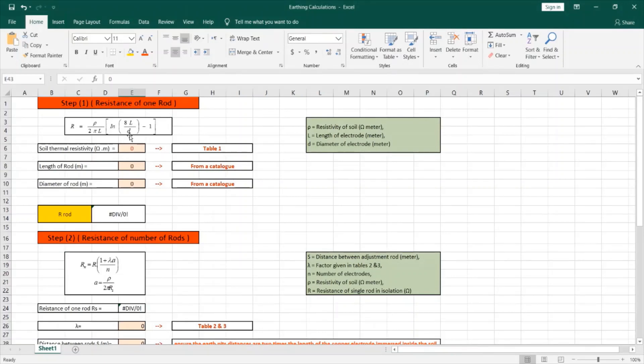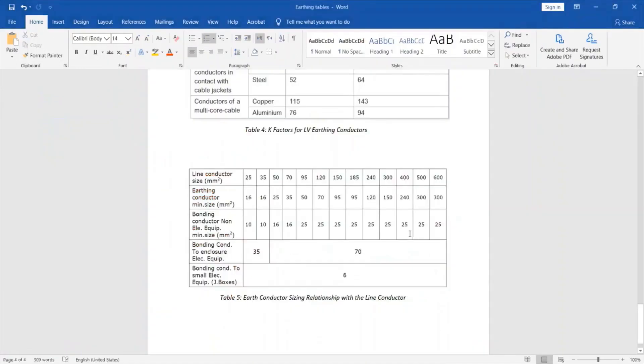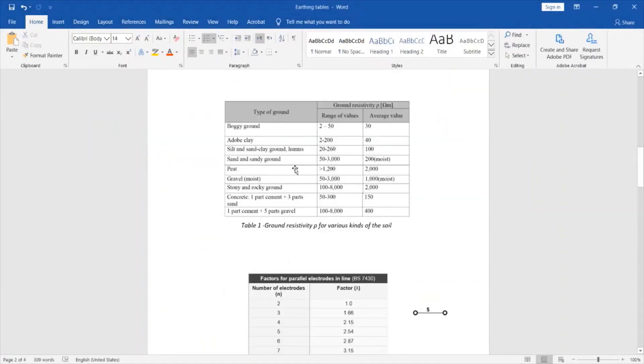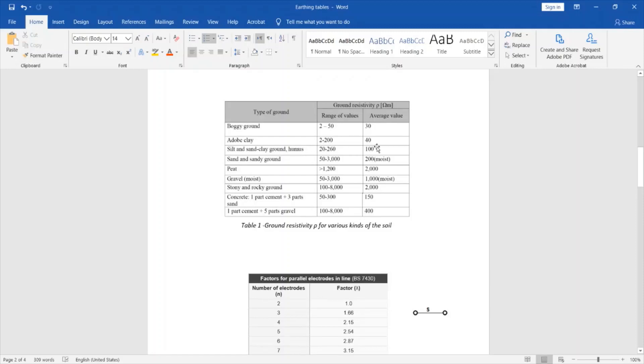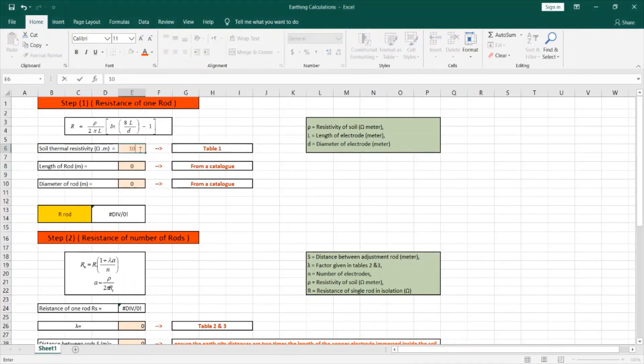Now let's apply these steps by solving one example. For Step 1, we need to enter the soil resistivity in ohms per meter. By referring to Table 1 and supposing that the project is located on silt and sand-clay ground, the average value is 100 ohms per meter. So I'll enter 100 ohms. Next, to enter the length and diameter of the rod, we can obtain these accurately using a manufacturer's catalog, so let me open the catalog.